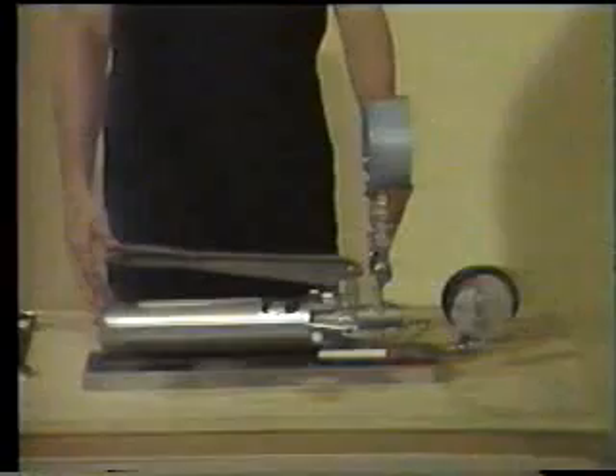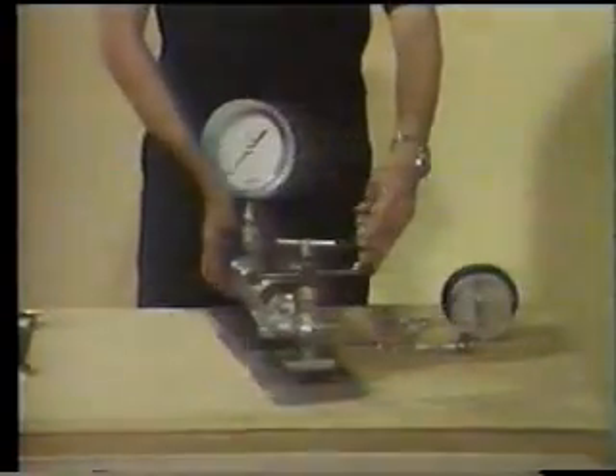Next, remove the master test gauge assembly from the manual shut-off bleed and instrumentation valve. Reinstall the protective cap. Then tighten the cap and open the valve. When the calibration of the gauge is complete, document discrepant items, return the unit to service, and perform a leak check of connections used during gauge calibration. We will now go to the lab and demonstrate gauge adjustment.